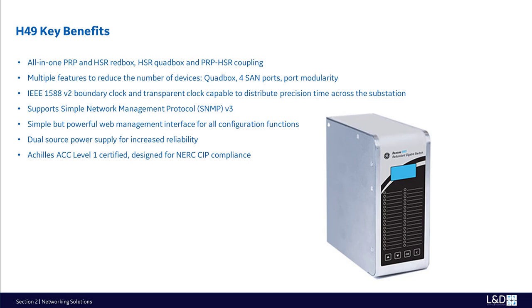IEEE 1588 v2 boundary clock and transparent clock capable, to distribute precision time across the substation network and PRP HSR boundaries, saving the cost of cabling used to deliver IRIG-B based signals. Supports Simple Network Management Protocol SNMP v3 with full backwards compatibility for V1 and V2. Simple but powerful web management interface for all configuration functions, like those used in the S20 switch. Dual power supply for increased reliability, and Achilles Level 1 certified, designed for NERC CIP compliance.